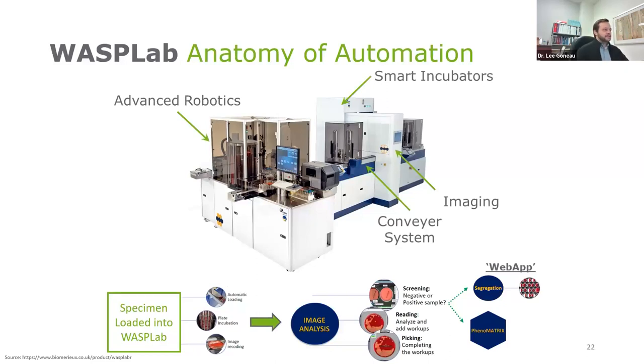This is how the WASP Lab works in a nutshell — very similar to how the BD Kiestra might work. At the front end, you have advanced robotics where all the plates are managed and specimens are loaded and planted. They're then fed along your conveyor system to the smart incubators, which are closed incubators with very optimal growth conditions for bacteria. When they're done incubating and ready to be imaged, they go to the imaging module. Walking through the workflow: the specimen is loaded into the WASP, it's planted, incubated, the image is recorded, and then you go to image analysis. You have options — you can do screening on the web application with separate workflows, or you can use the machine learning AI component called Phenomatrix to do that work for you.